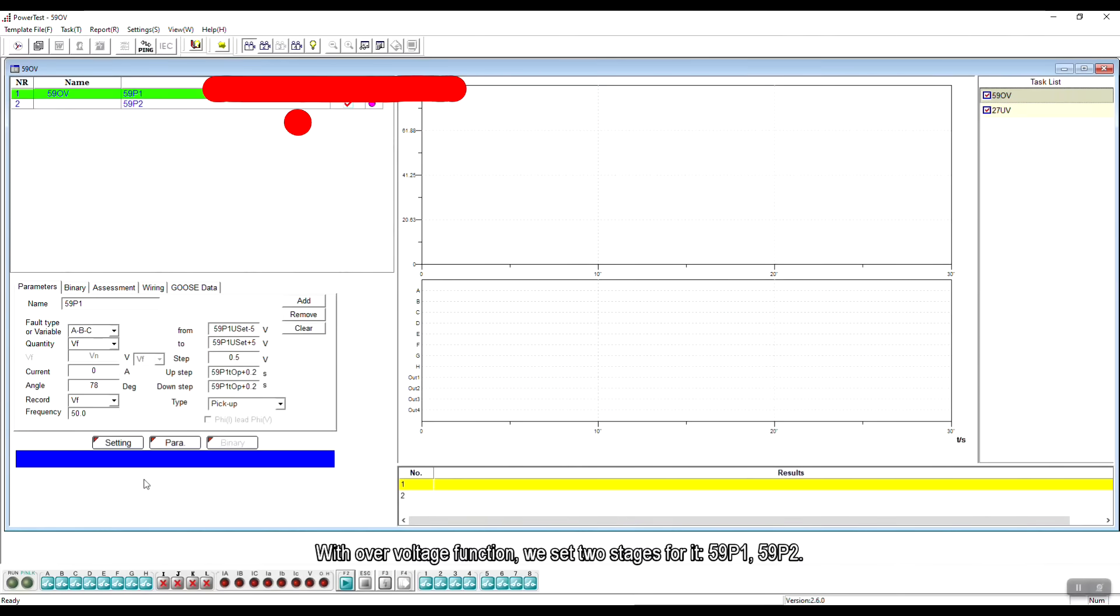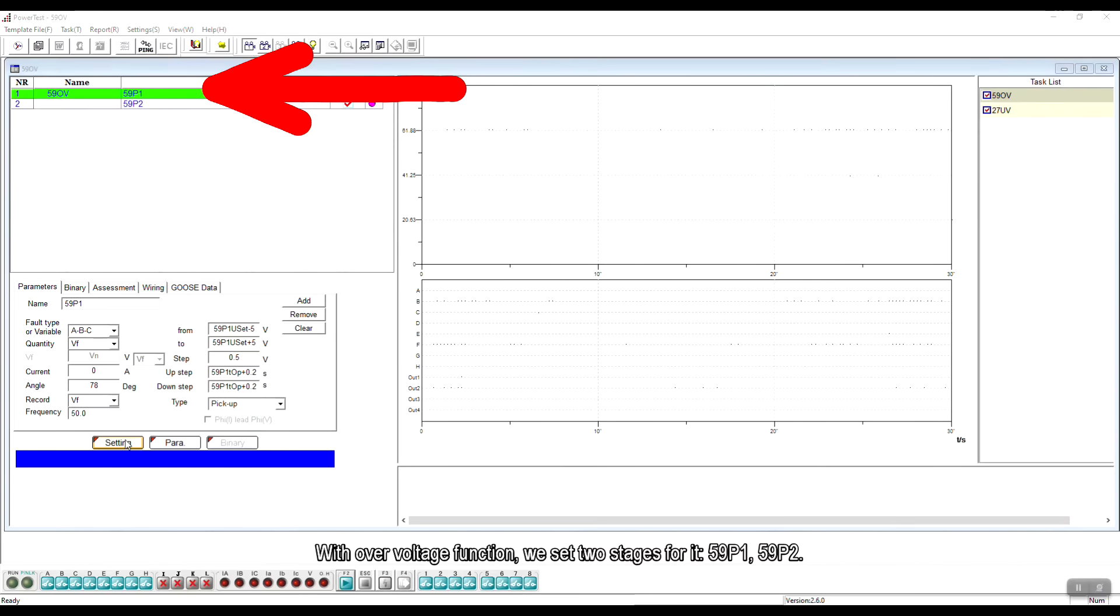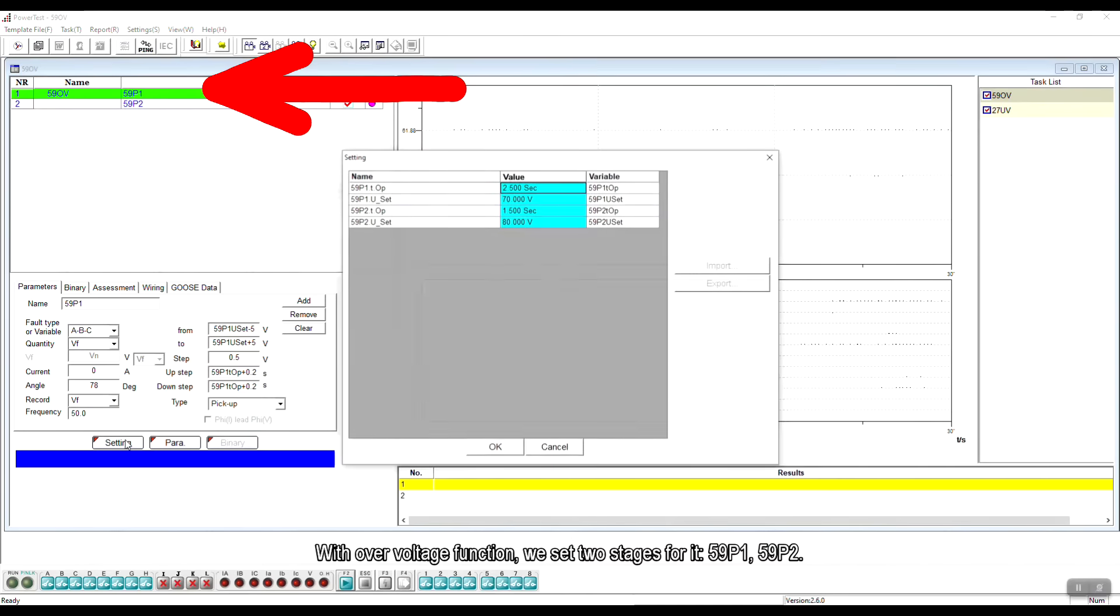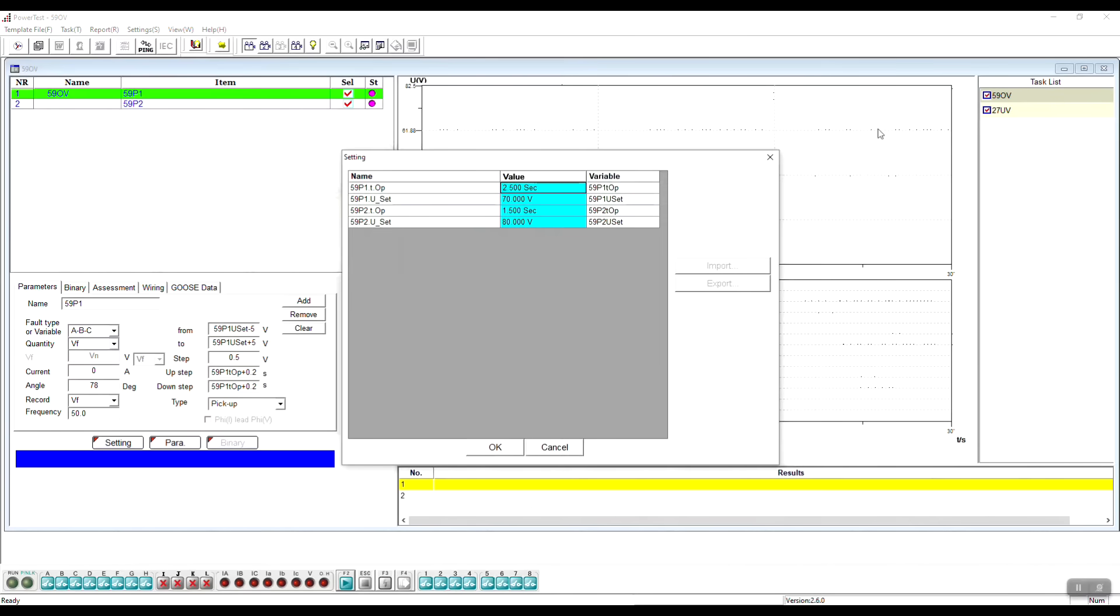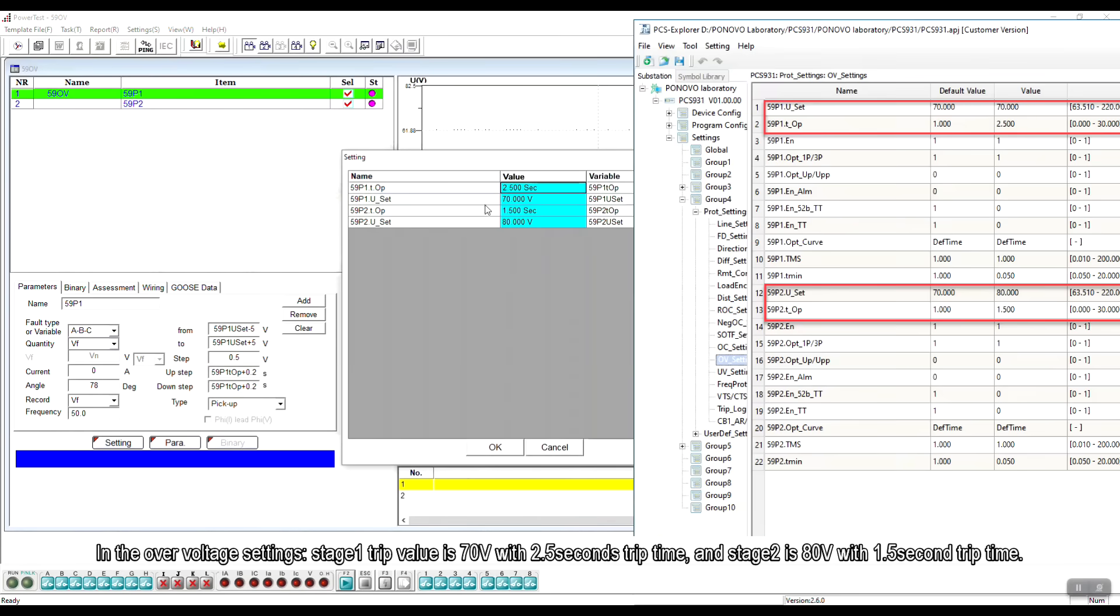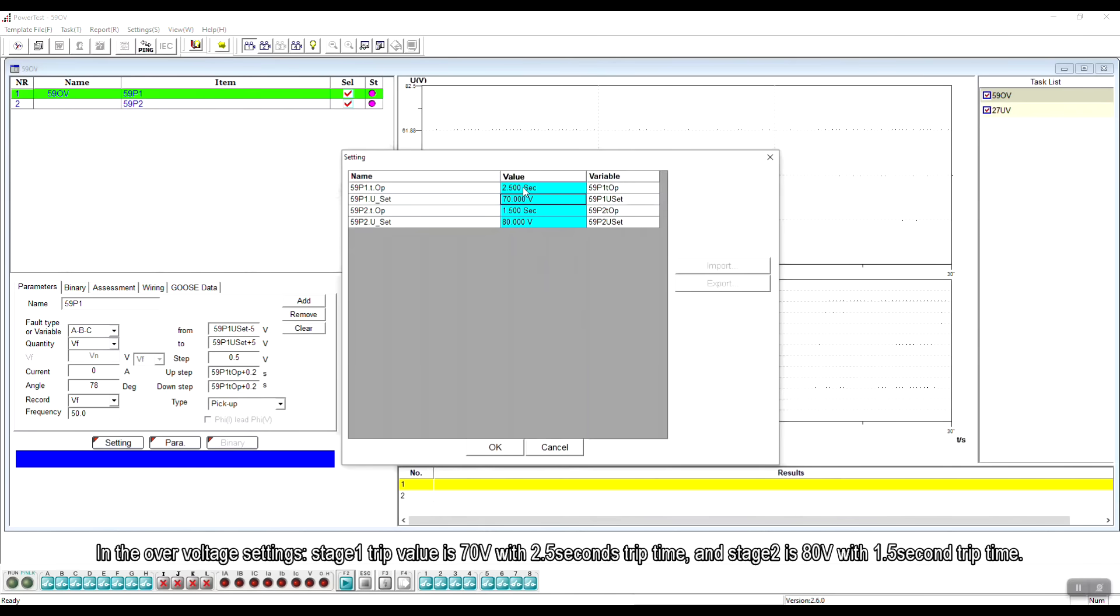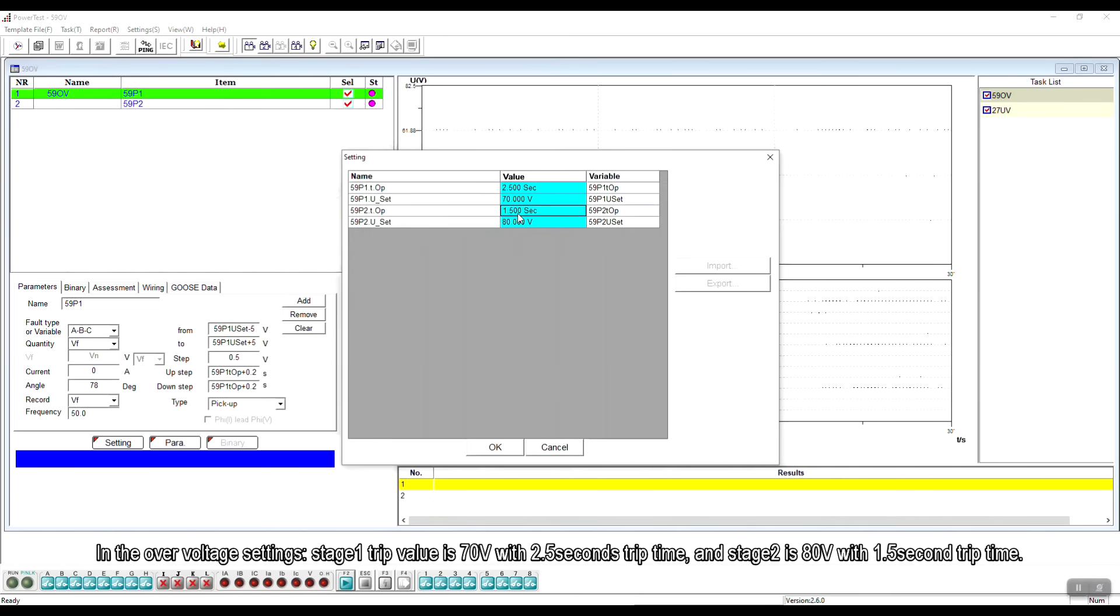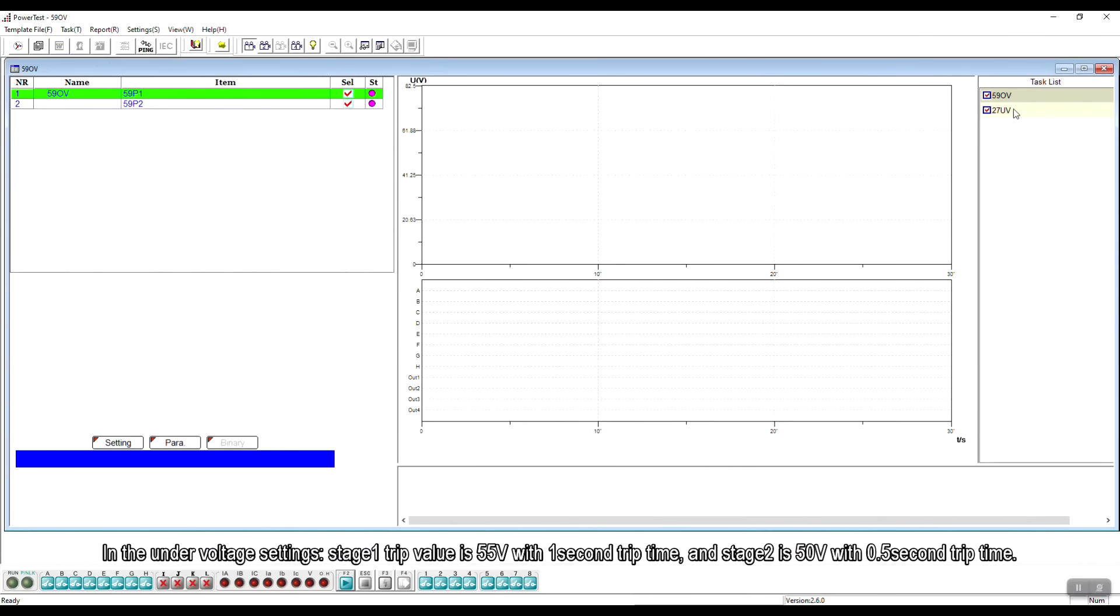With over-voltage function, we set two stages for it, 59P1 and 59P2. In the over-voltage setting, stage 1 trip value is 70V with 2.5s trip time and stage 2 is 80V with 1.5s trip time.